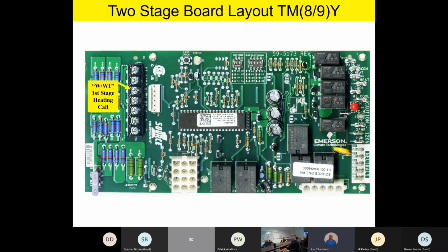Now remember, team, this is a 2-stage heat, 2-stage cool board. So if you're stuck with a single stage thermostat, you always want to land that W call from the thermostat on this W/W1 terminal. The reason is we can give you some staging later on with some dip switches. So if you do have a single stage thermostat, just land your W wire on this W/W1 terminal. If you have a 2-stage thermostat, W2 will be our second stage heating call from the thermostat.